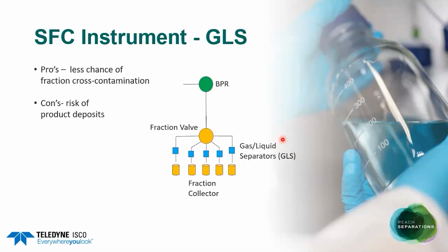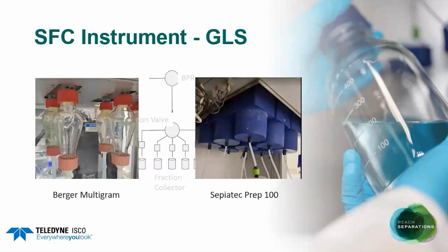In this situation, you very much reduce the chance of any cross-contamination of your fractions. However, due to the flow intermittently passing through each GLS, you can get deposits of material on the internal surfaces of the GLS, particularly for low soluble samples. Now, examples of this type of configuration in our labs are shown here. On the Berger Multigram on the left-hand side, we have gas-liquid separators, so it's quite easy to see any build-ups of material. On the Sepiatec Prep 100, the gas-liquid separators are housed behind this blue styrofoam here, and so you can't see them. So you do have to be quite careful with cleaning down procedures. Both of these systems are examples of what we call impact separators, where the gas-liquid mixture impacts on the surface, causing the gas and the liquid to be separated.